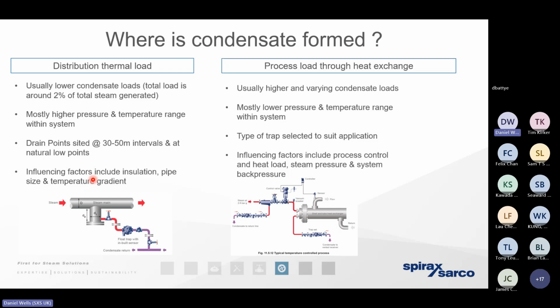We're going to get more heat loss if we've got especially wet steam. Drier steam isn't going to condense as readily in the infrastructure. The question is, how much condensate do we need to remove? Now, we could go back to first principles and calculate the heat loss of the pipework and each individual component. In reality, we're not going to do that. It's a pretty thankless task. In reality, we're going to apply a rule of thumb, and that rule of thumb states that approximately 2% of all of the steam that is generated is going to condense out in the infrastructure before it gets to the point of use. So if we're generating 10,000 kilograms of steam per hour, we expect 2% or 200 kilograms of steam to condense out in the pipework.